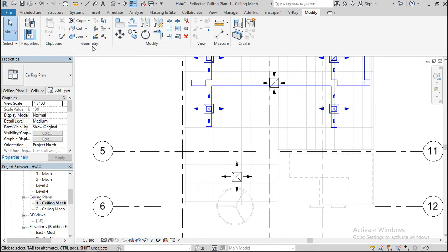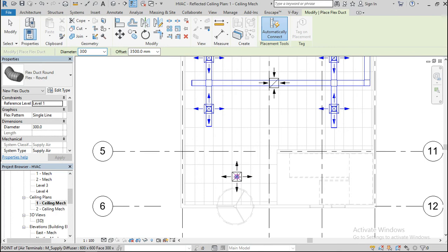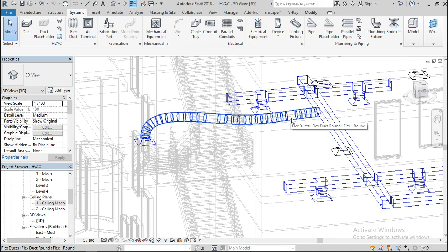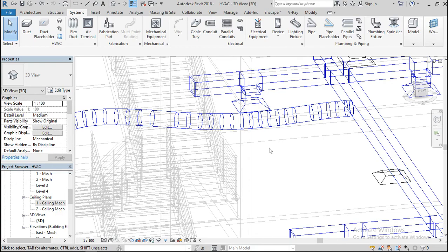So sometimes to reduce cost, we use flexible ducts. These flexible ducts are very, very good. The flexible ducts help in cost reduction because this is much more expensive than this one, but this one is much more durable in time than the flexible duct. Sometimes the flexible duct will deteriorate with time, so you end up having leakages in your system. But for this one, it lasts for a long period of time.